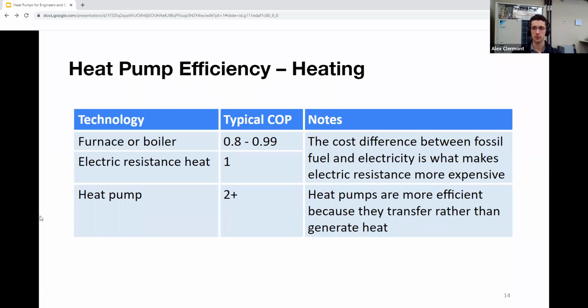So now we just want to talk about the COP comparison between traditional forms of heat and heat pumps. And as you can see here, heat pumps are more efficient because they don't generate heat, they actually transfer heat from one space to the next. Something as well to keep in mind with a furnace or a boiler: the reason we have COPs in that range is because that COP doesn't take into account the energy required for pumps or fans to actually blow or pump water around. Let's say it was a boiler. That COP is just looking at the furnace itself. So electric resistance heat is also just the baseline metric with the COP of 1.